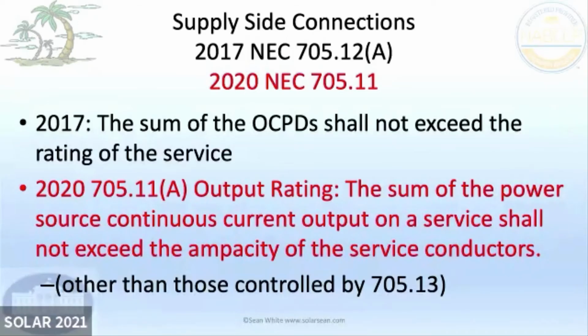Now what we're going to do is look at some of these interconnections. When we do a lot of NEC classes, we get kind of deep into this. They did change some things for supply side connections. The most noticeable thing they changed from the 2017 to the 2020 NEC is the numbering. It went from 705.12(A) in the 2017 version to 705.11, so it's got its own place there.